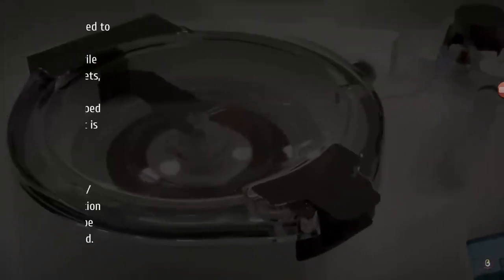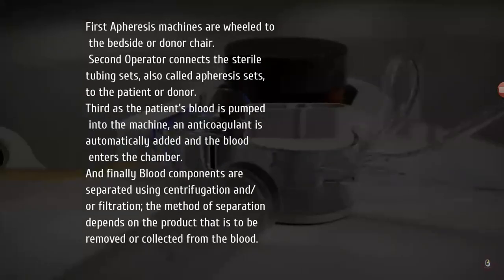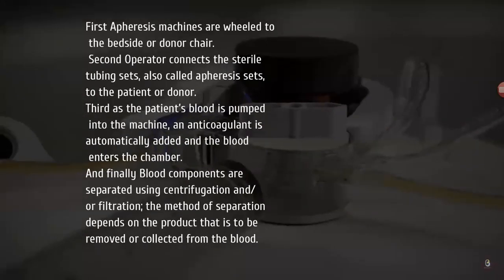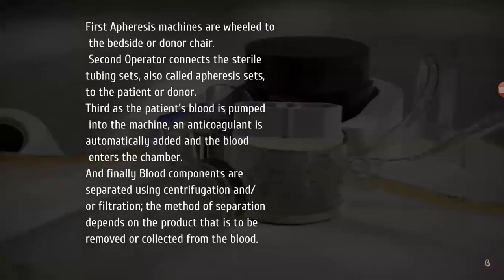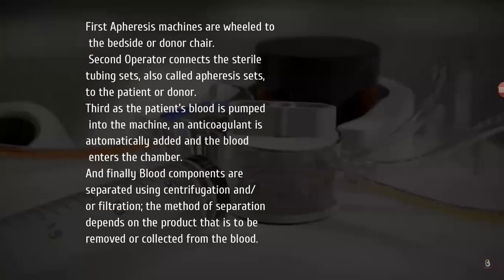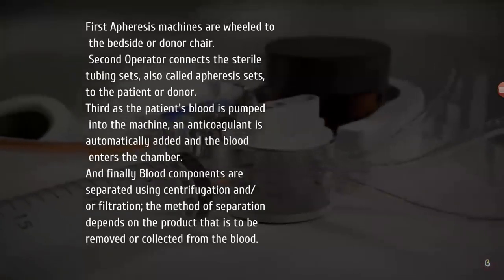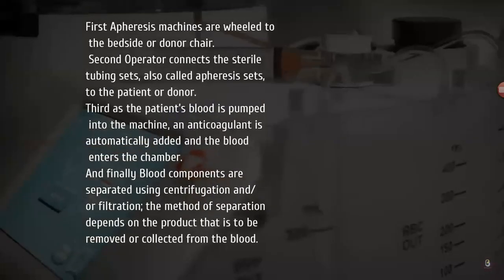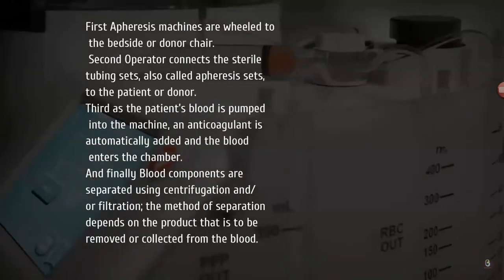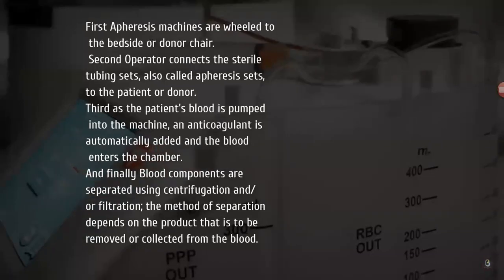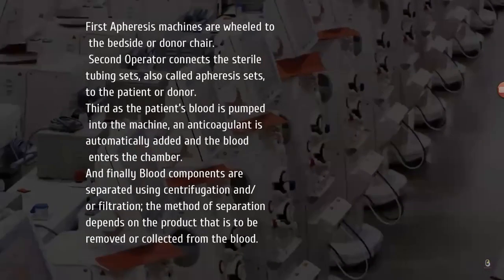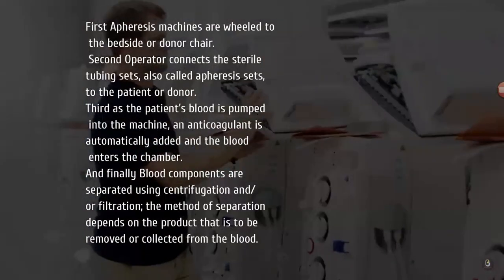First, the apheresis machine is wheeled to the bedside or donor chair. Second, the operator connects the sterile tubing sets, also called apheresis sets, to the patient or donor. Third, as the patient's blood is pumped into the machine, an anticoagulant is automatically added and the blood enters the chamber. And finally, blood components are separated using centrifugation and/or filtration. The method of separation depends on the product that is to be removed or collected from the blood.